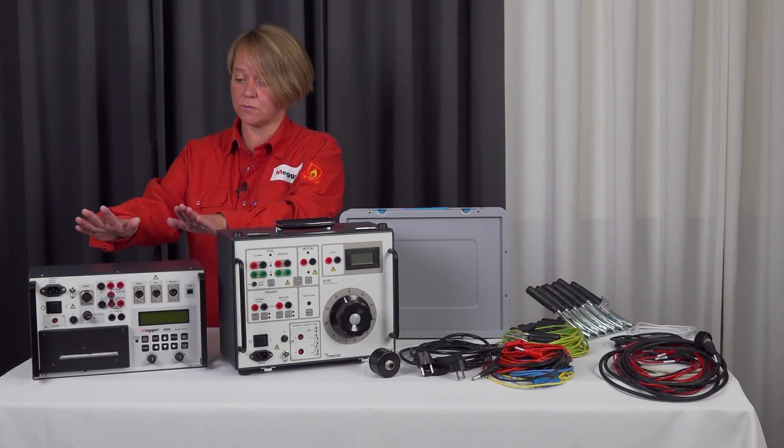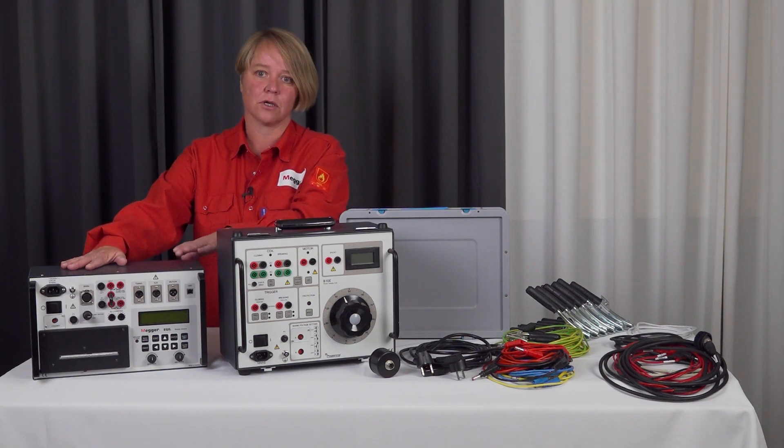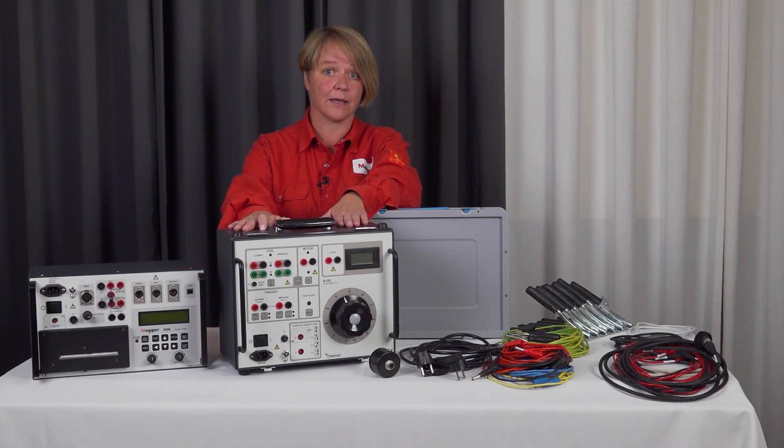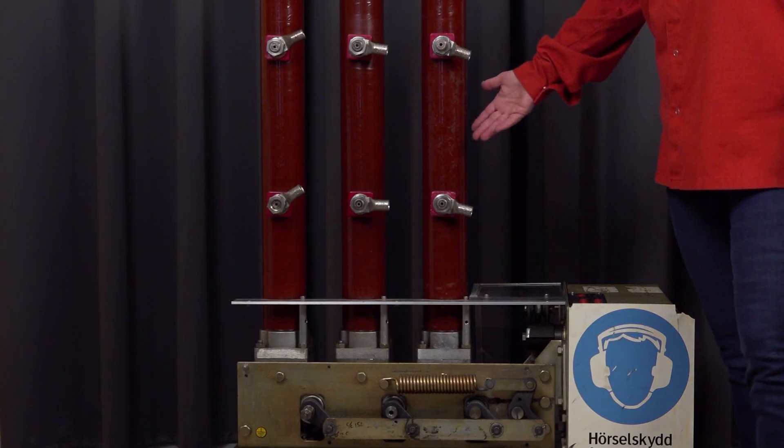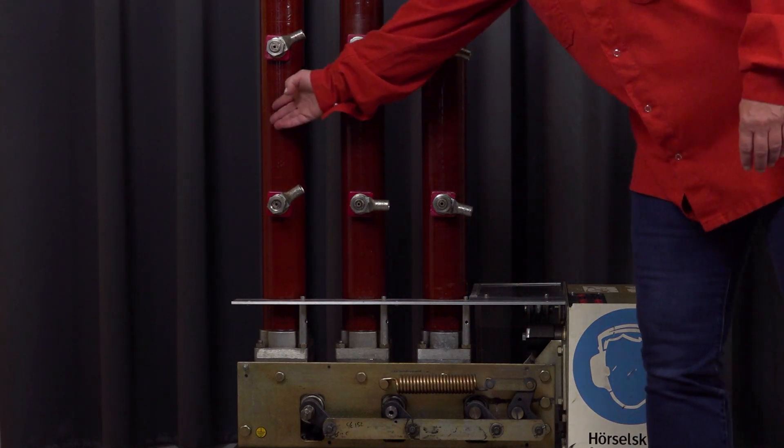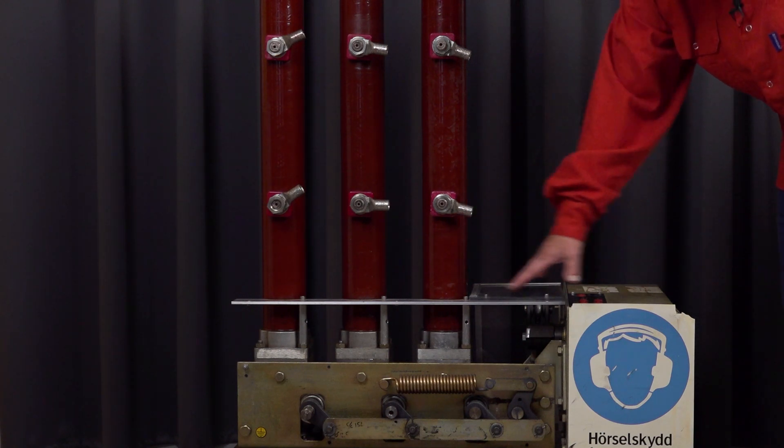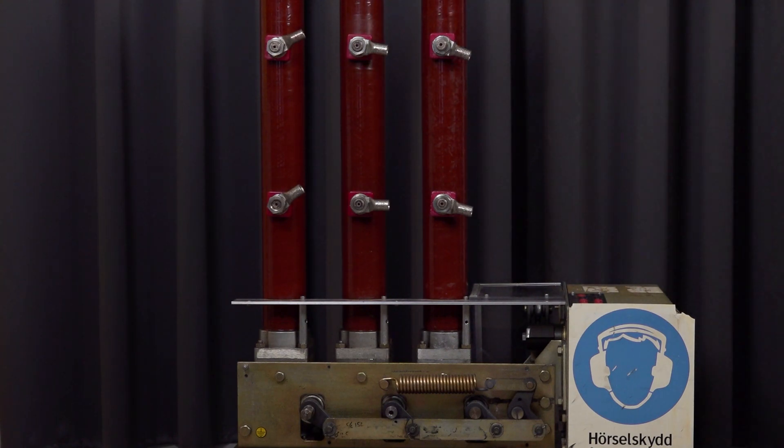EGIL is a small timer which can do timing, motion, and also measure the coil currents. Today we're also going to use B10E which we need to supply the coils and also the motor charging. We're going to measure on a circuit breaker, a 12 kV medium voltage breaker. It has three phases, the upper and the lower contacts. It has a motor mechanism, a common mechanism for all three phases.